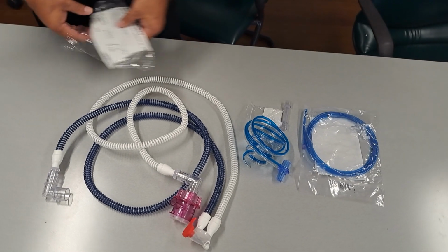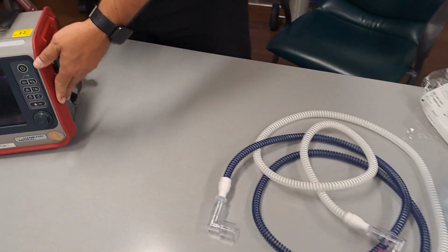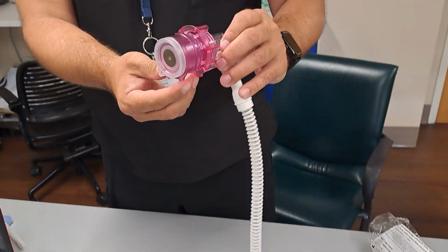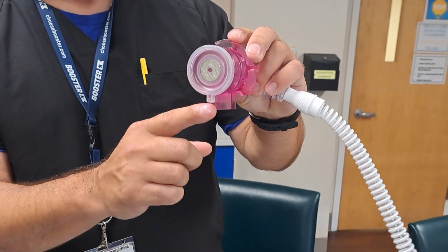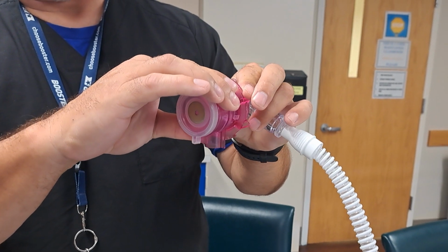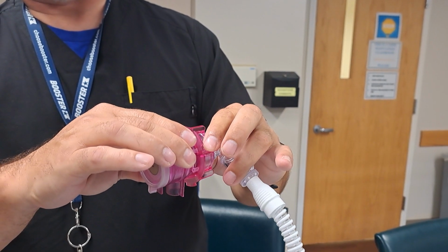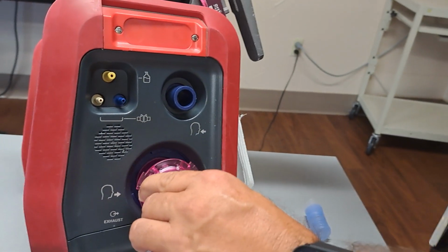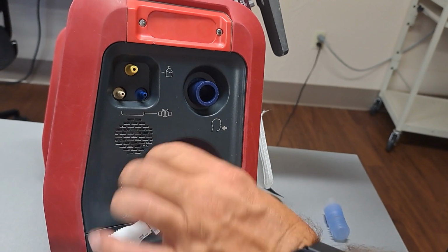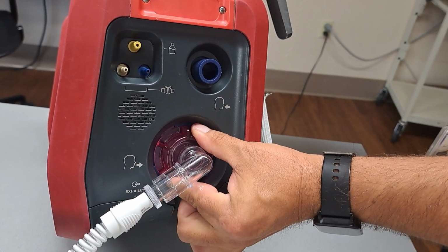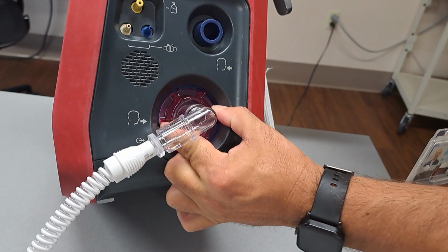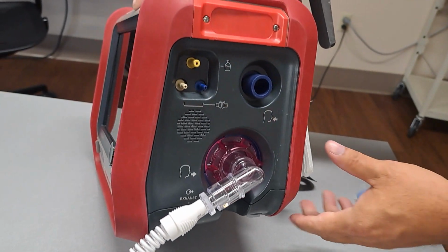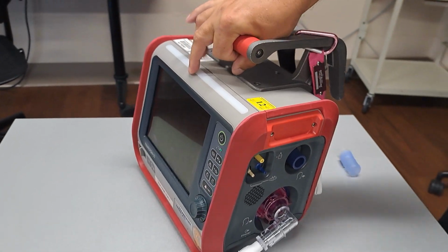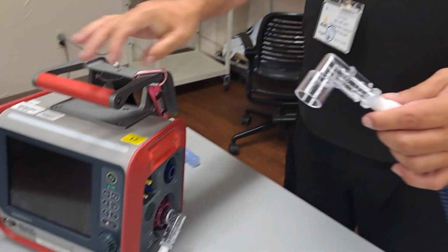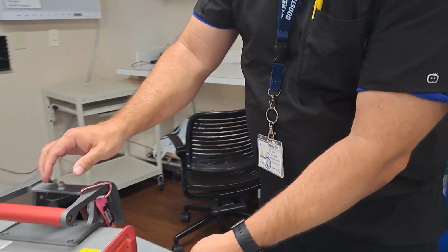So now let's look at how we connect the circuit to the ventilator. First, we'll connect the exhalation valve. And as you see, the exhalation valve has a spout down here. There's only one way that it can connect. And you want this knob turned all the way to the left so that when you go to connect it to your exhalation valve, it just slides in like this, all the way down, and then you turn this clockwise to lock it in place. Okay? So that's your exhalation side of the circuit and the exhalation valve. Then your inspiratory line connects right here.